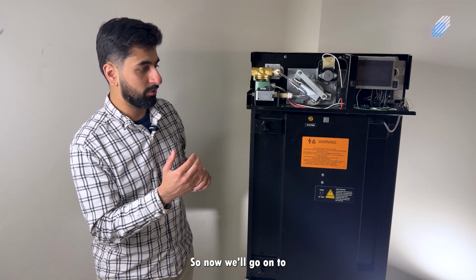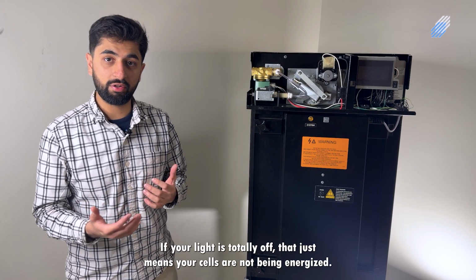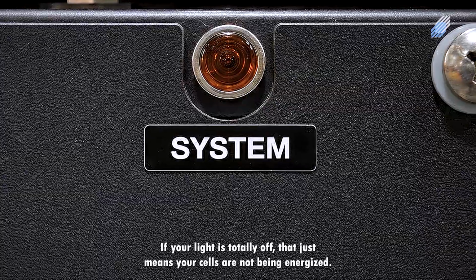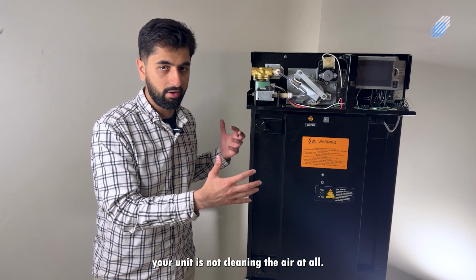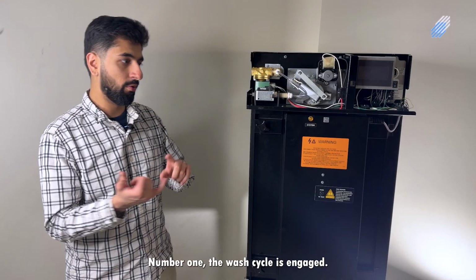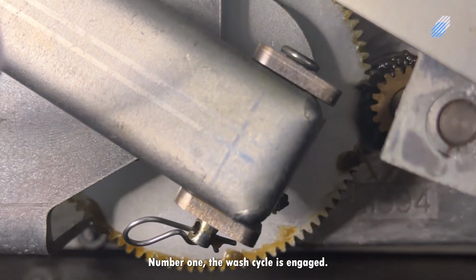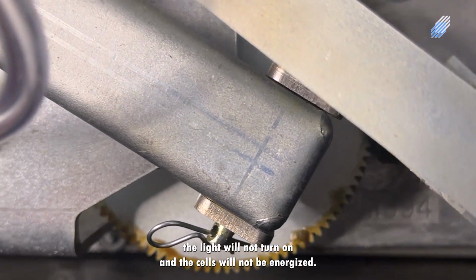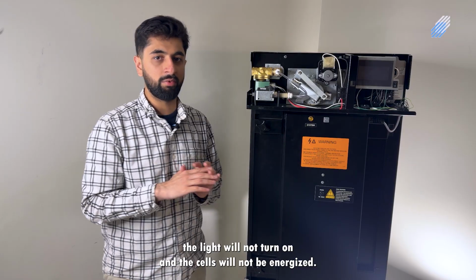So now we'll go on to if your light is off. If your light is totally off, that just means your cells are not being energized. Your unit is not cleaning the air at all. That could be because of a multitude of reasons. Number one, the wash cycle is engaged. If the cells are being cleaned, the light will not turn on and the cells will not be energized.